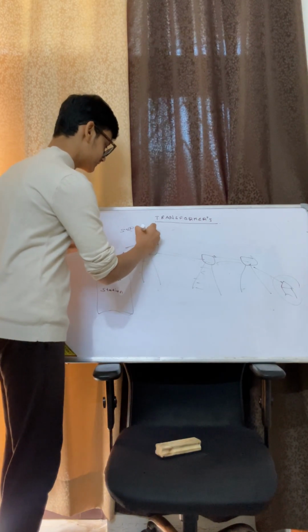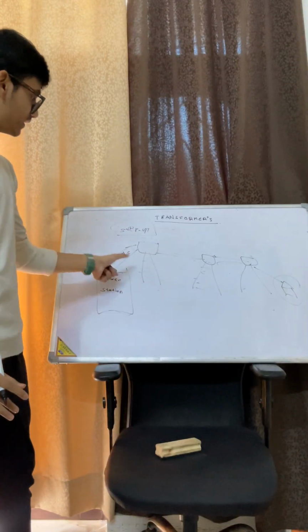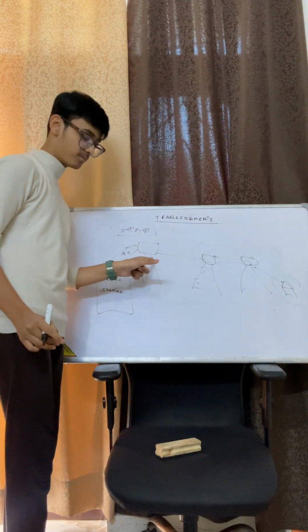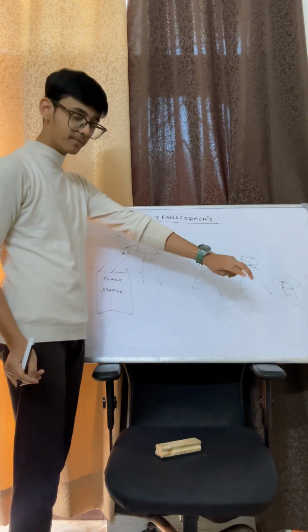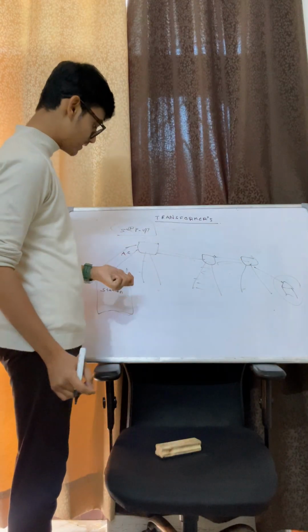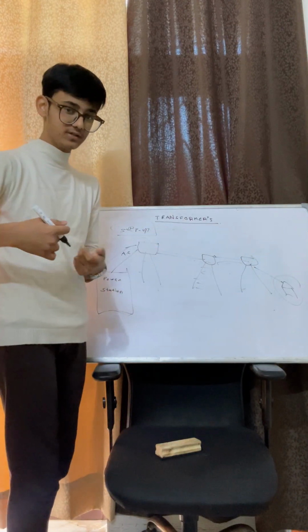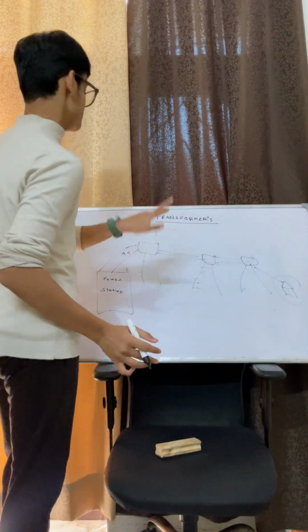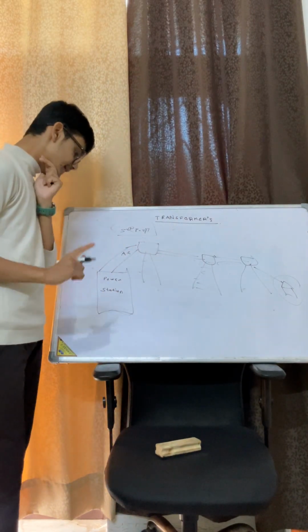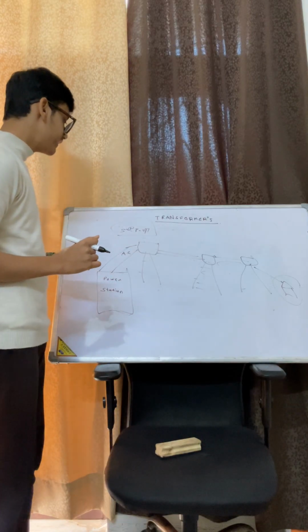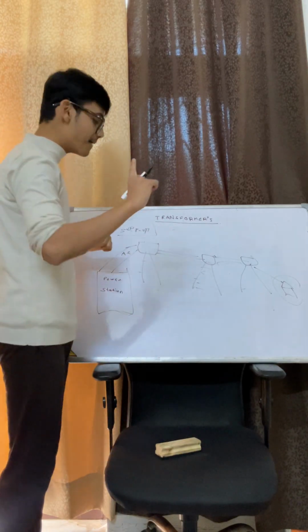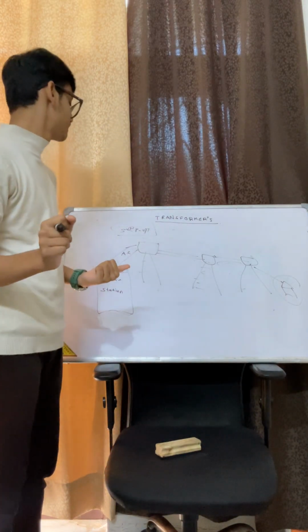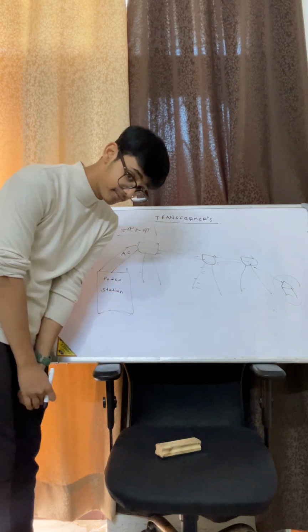Step up transformers. These right here are step up transformers. When the power station has to transfer power through power cables, this is a step up transformer. So what a step up transformer does is that it will step up the voltage and step down the current.